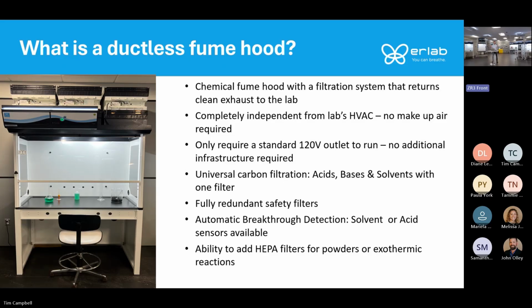It has 3 filtration columns. So if you look at the top of the picture, it looks like a double stuffed Oreo, as my colleague Julie likes to call it. And the white, the cream part, those are the fans. So that's what's driving the air away from the user into the filtration column. Below the fan, there's our main carbon filter or primary carbon filter. That's what's doing all the work, capturing all those chemical vapors and fumes that are generated within the enclosure.